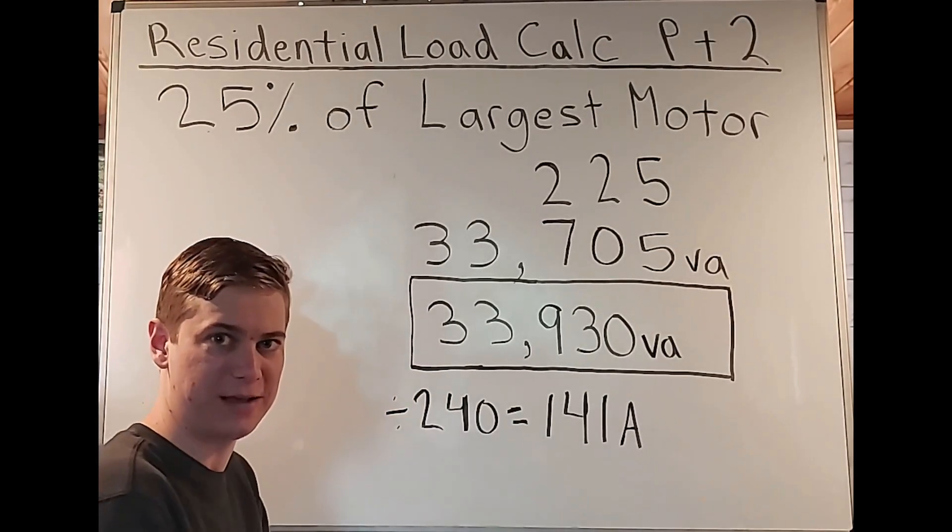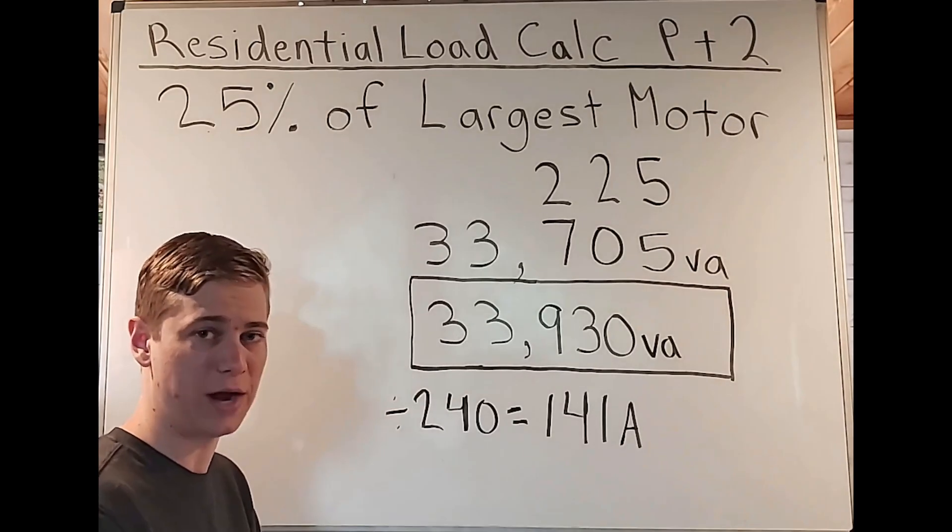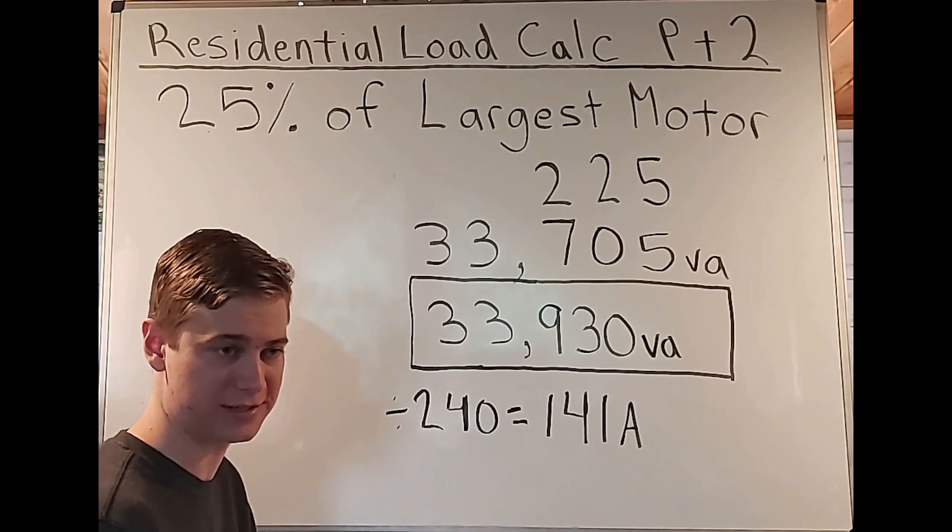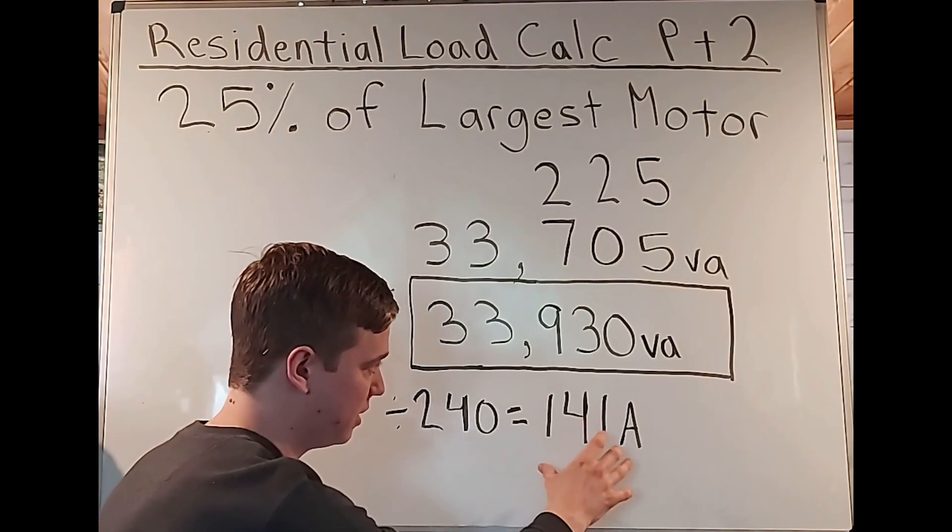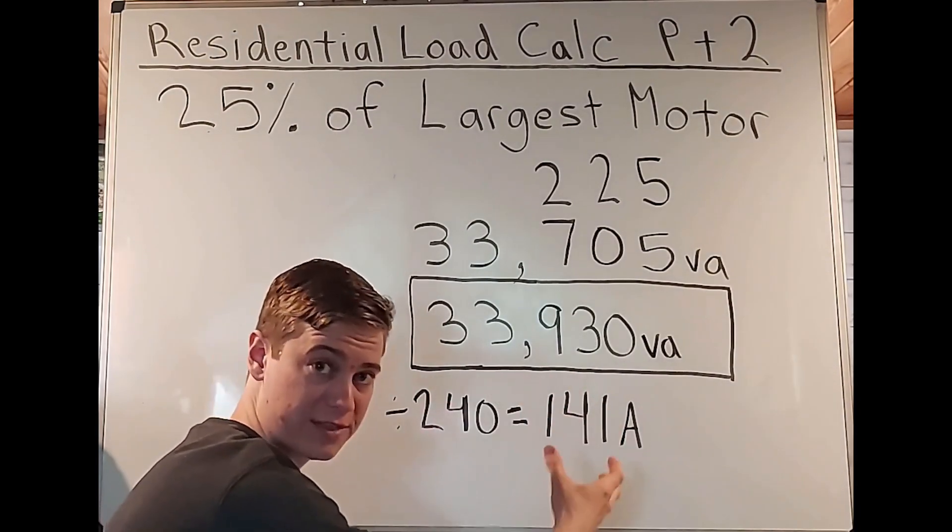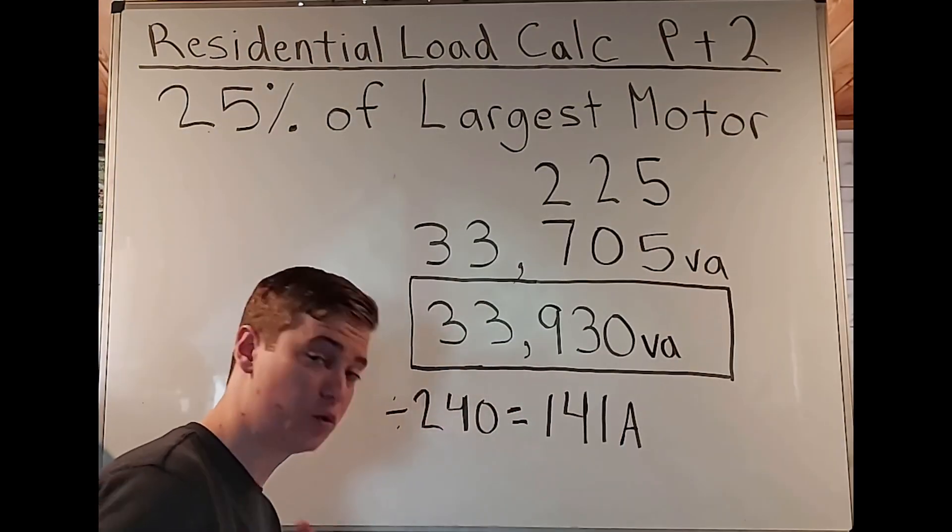So logically speaking, we'd probably size down. But the thing is, if you've done this enough times, you know that you normally size up. Now we have to ask ourself, why are we sizing up? If we're looking for an overcurrent protection device, this is supposed to be protecting us from overcurrent. So we should probably size to the current that we have and not more than that.